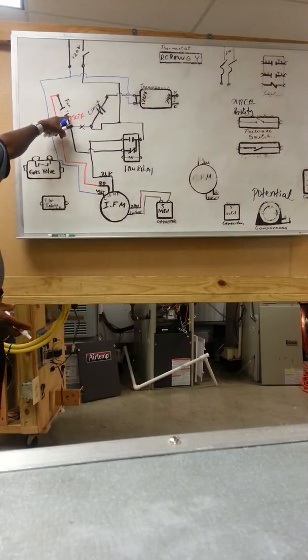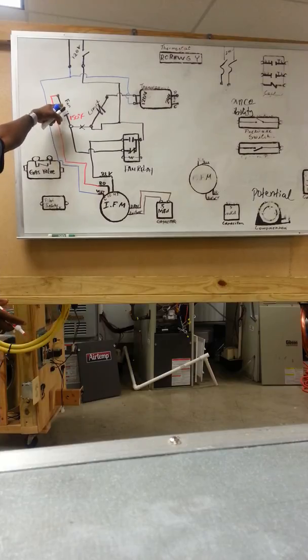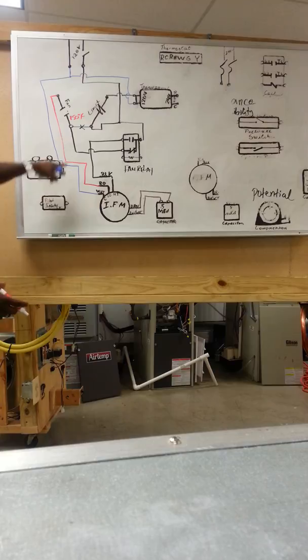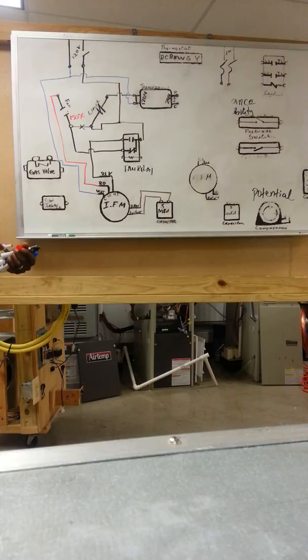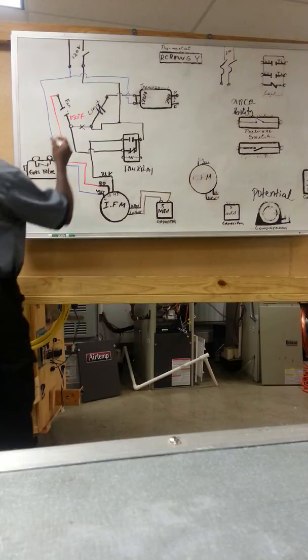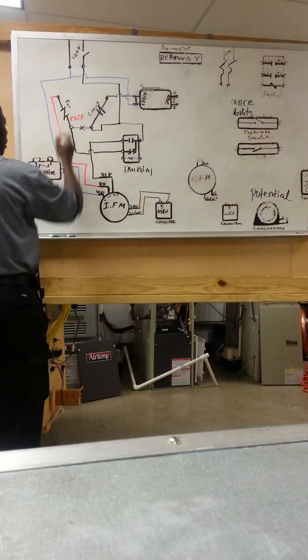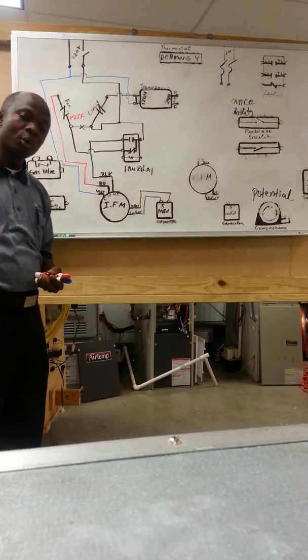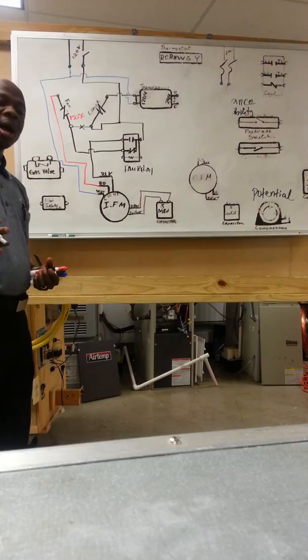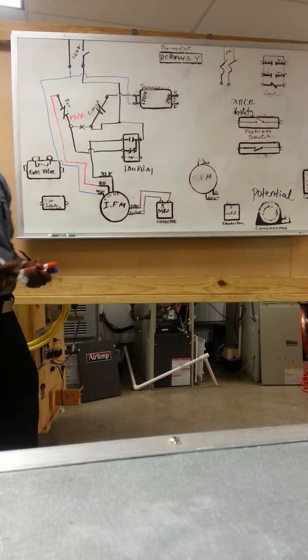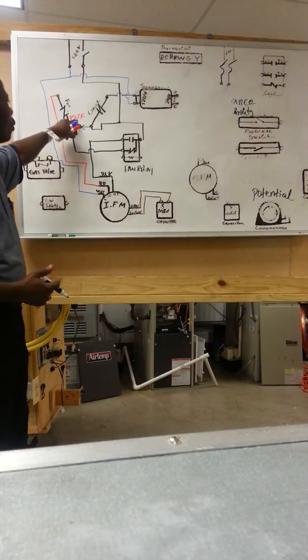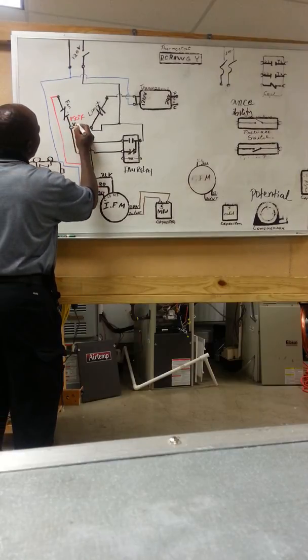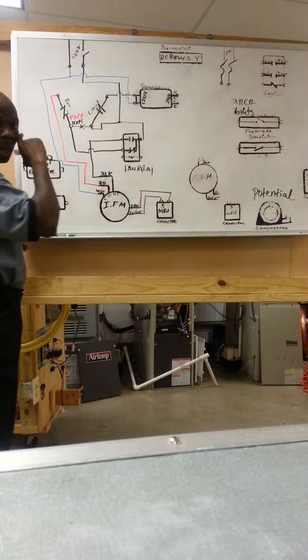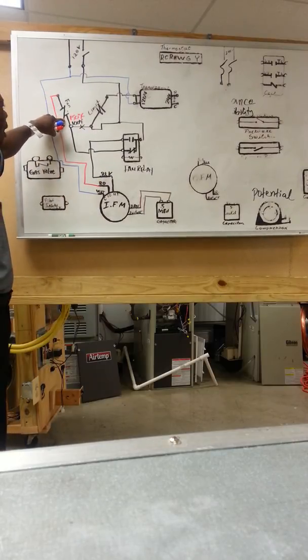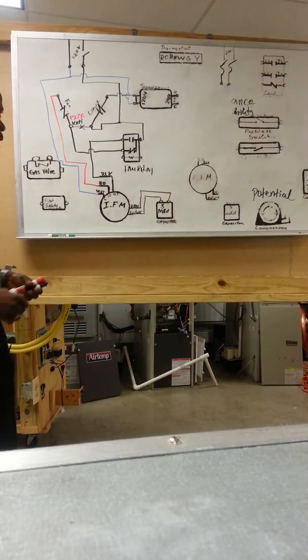Now once that 150 degrees is activated here, it will energize and close that fan side. Now we're going to have 120 volts going to the fan, and the fan is going to come on in the heating cycle. So let's go ahead and close this, assuming we have heat coming in. Once the fan blows, it is going to cool that fan switch down. After the thermostat has reached its temperature, it's going to cool it off to 100 degrees Fahrenheit. For this older unit at 100 degrees Fahrenheit, now this is going to de-energize and open the circuit again, and the fan is going to go off.